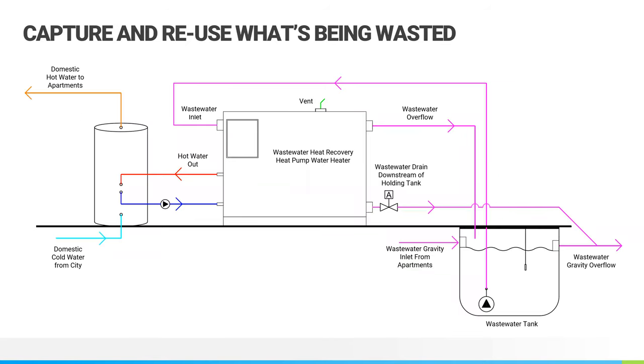So really what's going on in that building is as that wastewater is leaving the building, there's a tank that captures that wastewater. And as the building calls, people get up in the morning, 6 o'clock, everybody starts showering, it's going to call for domestic hot water, and it's going to call for heat. So that's when we're going to pump wastewater into the heat pump water heater. And then the heat pump transfers the energy from the wastewater, through refrigerant, to the water. That's what's going on inside. And then that's when you're going to get the domestic hot water out to the apartments. And then as that temperature degrades inside the water heater, a valve opens, the water is rejected back out to your sanitary wastewater, and the wastewater tank process starts all over again, where we refresh with warmer thermal energy.